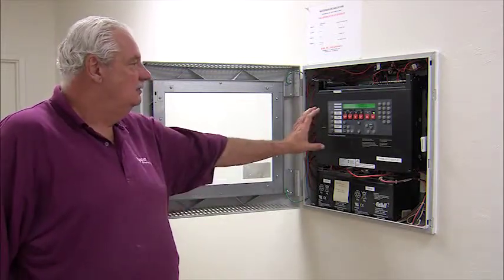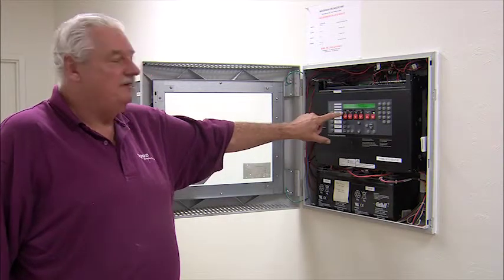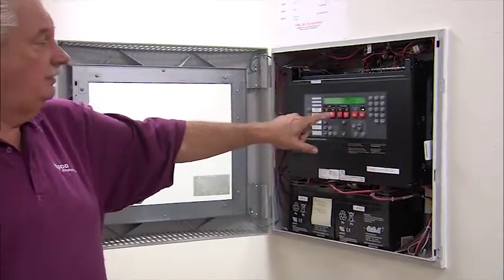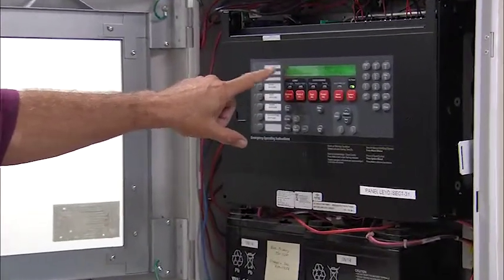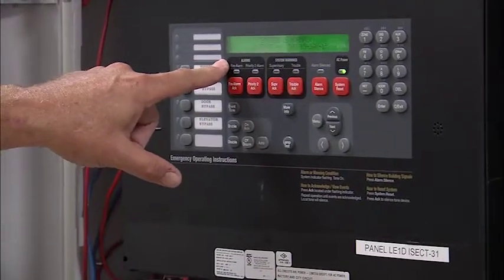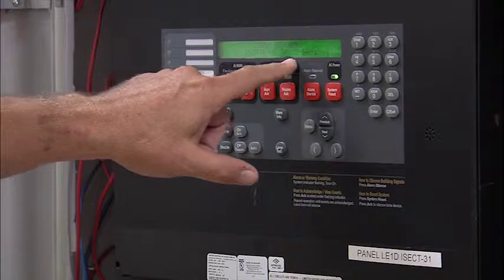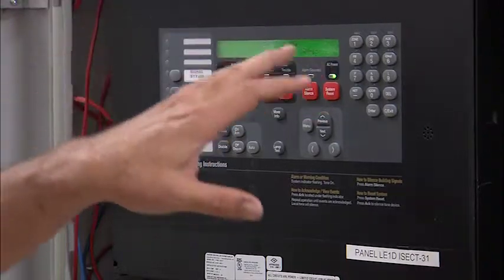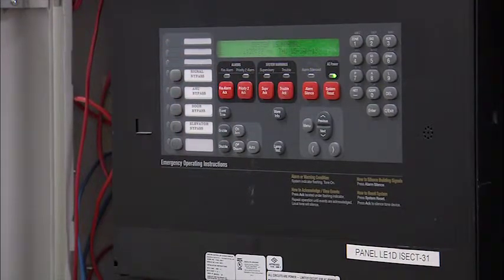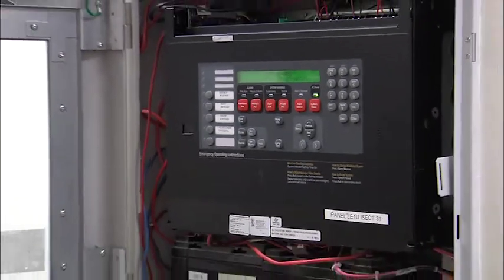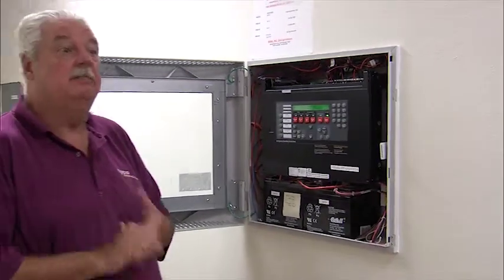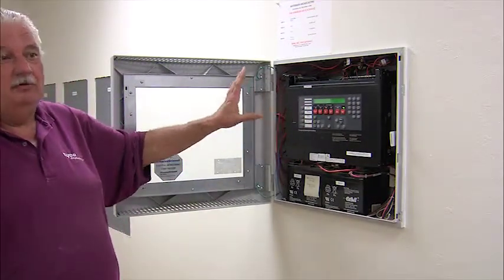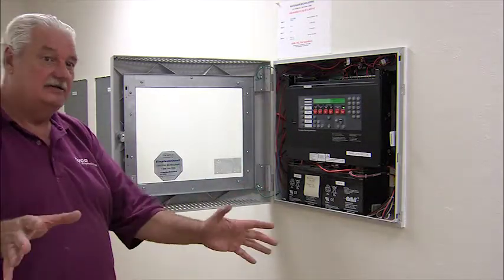Okay, the third item that happens is a fire alarm. Okay, fire alarm is going to sound all the horns in the building. It's going to light this red light. Okay, anytime that goes off, your first priority is to evacuate the building, especially the area that the fire's in. Now you have another one of these that is mimicked up by the reception, so she should be able to read that and tell what area it's in. It could be a pull station, it could be a smoke detector, it could be one of the other panels. Main priority is exit the building, okay? Do not silence it. The fire department will frown upon that. I understand you guys have a little different situation.